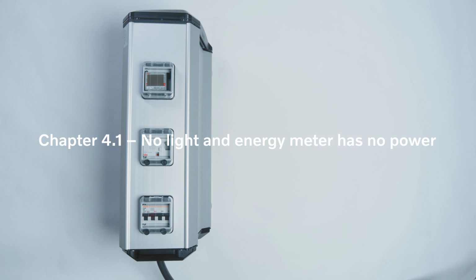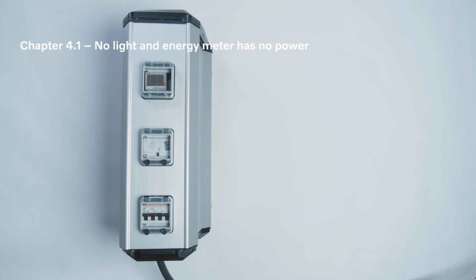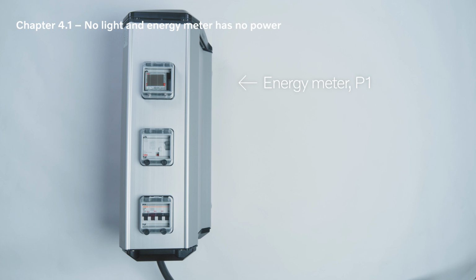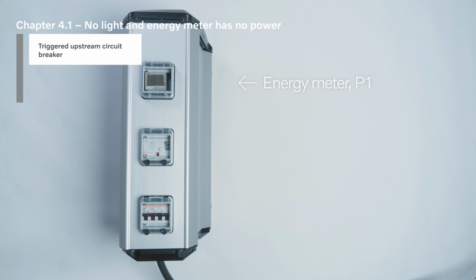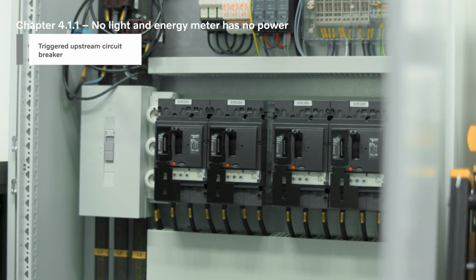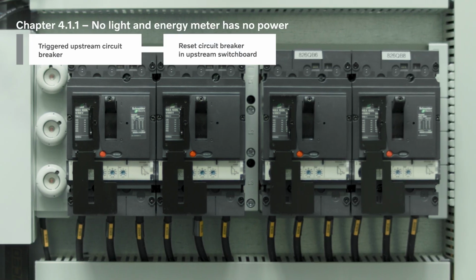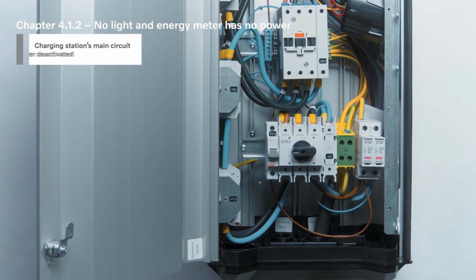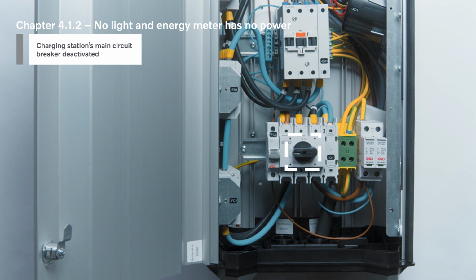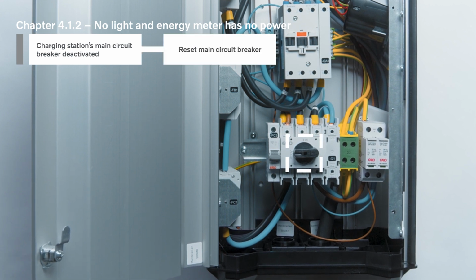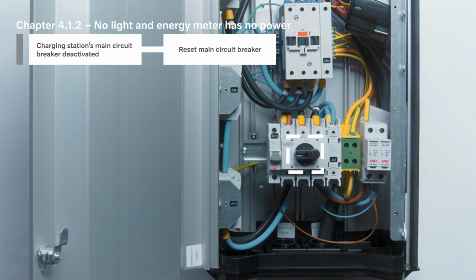If the LED indicator isn't displaying any light and the left side energy meter, P1, isn't displaying any numbers, the power failure may be caused by a triggered upstream circuit breaker, or if the main circuit breaker inside the bottom of the charging station is deactivated. If the problem is caused by an upstream circuit breaker, you should reset it in the upstream switchboard. If the issue is caused by the charging station's main circuit breaker, you should reset it. You find it inside the bottom of the charging station.